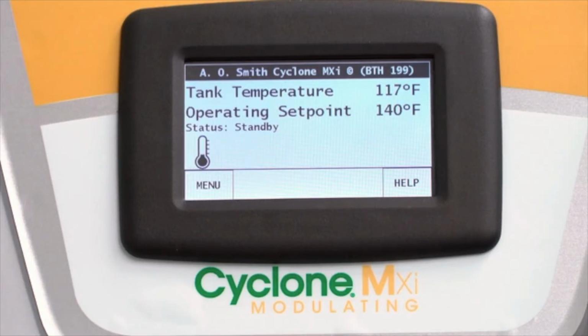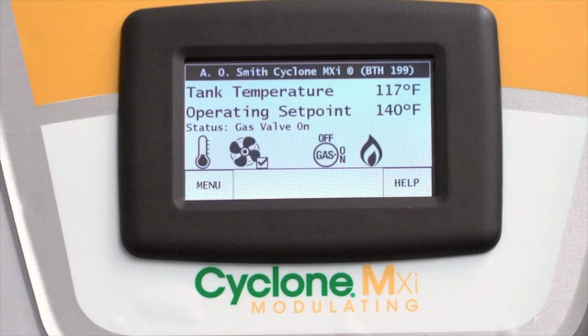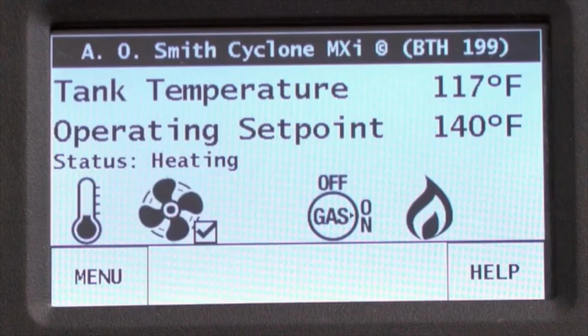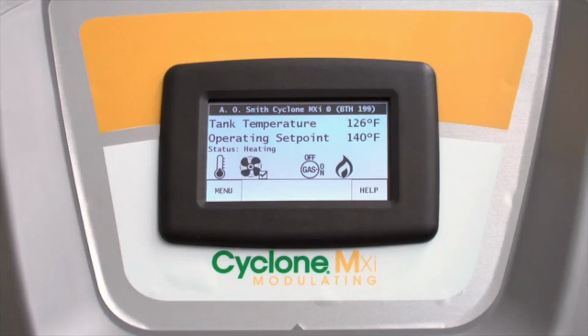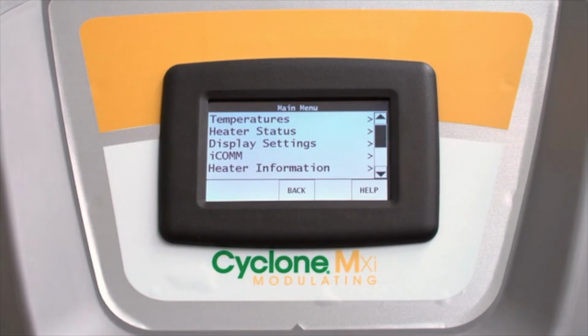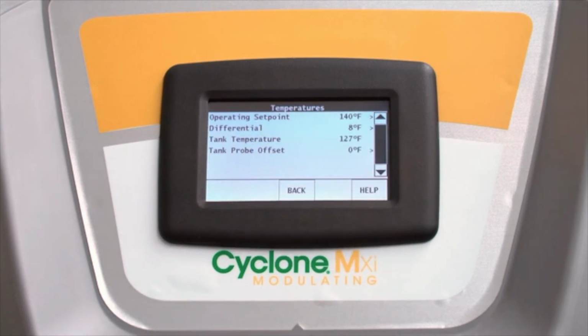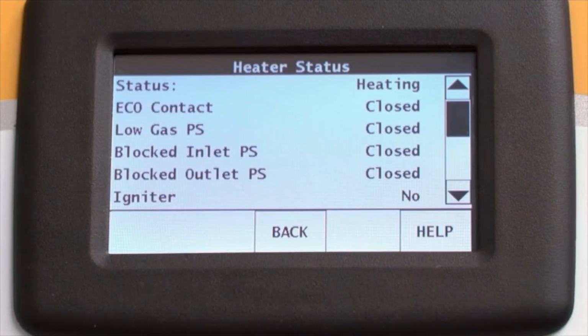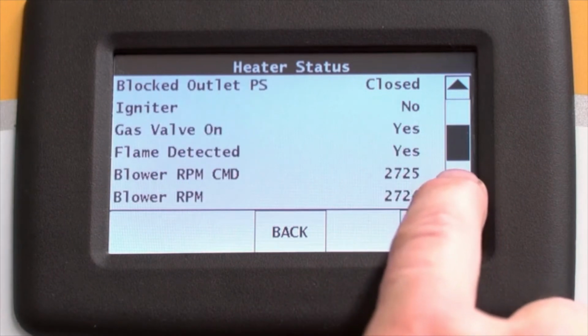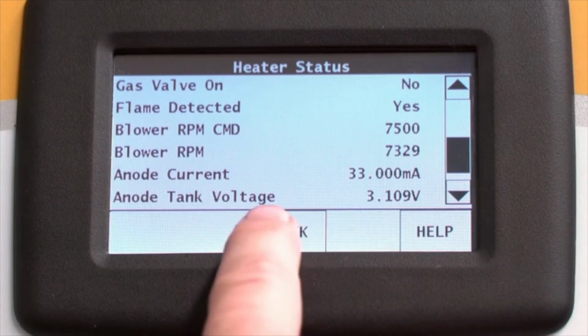The control defaults to the standby mode when the water heater is waiting on a call for heat. At a call for heat, the display will show the fan icon indicating the water heater has started the pre-purge mode. The igniter, gas valve, and flame icons let you know that the water heater has completed the firing sequence and is heating. Clicking on the menu button allows you to monitor or control various operating modes and parameters. The temperature option lets you view or change the current set point and differential. Heater status shows you the current state of pressure switches and other sensors. All of the information on the heater status tab is updated in real time.